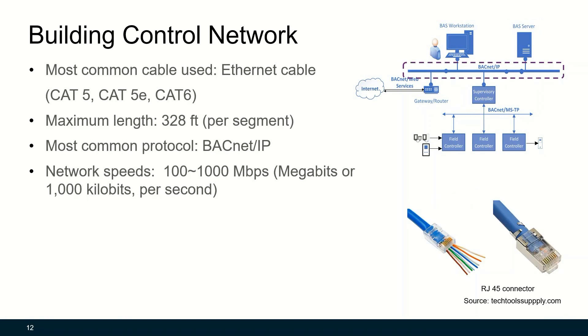The building control network connects BAS workstations, BAS servers, and supervisory controllers. The most commonly used cables are Ethernet cables such as CAT5, CAT5e, or CAT6. The maximum length is 328 feet per segment. The most commonly used protocol is BACnet IP.